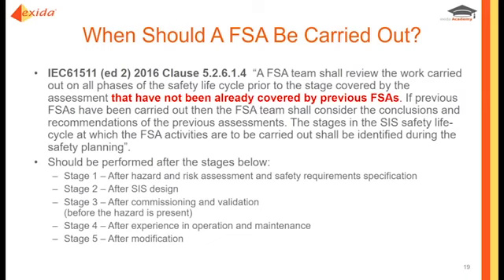So you could do this during FAT, for example, where you've got the hardware and the application software coming together for the first time. So that would be a good place to do FSA 2, to make sure again that what we've got in terms of the physical logic solver and the application software and the I/O is correct. And then stage 3, of course, is after we've done commissioning and validation. So that is very important. The standard now says that you need to, after you've been running for a while, and it says periodically you have to do performance assessment. That's the stage 4. So stage 4 is also mandatory.